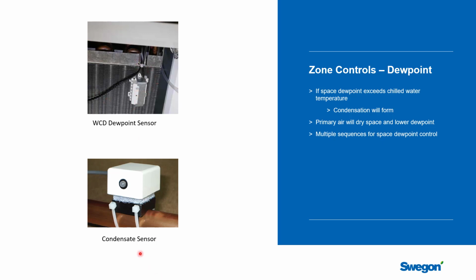Another approach that you'll see is a condensate sensor. Now this will have a pair of probes that are going to be in contact, typically, with the supply side of the chilled water piping, and that's going to be probably the coldest thing in a control zone. And so if the humidity is too high in this air, this is going to be the first place where you're going to see condensate start to bead on this pipe.